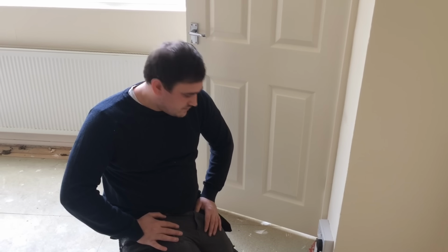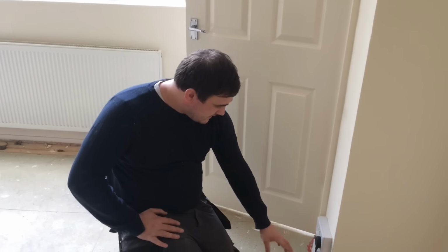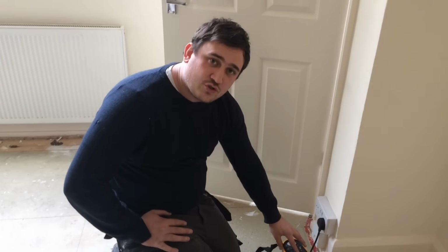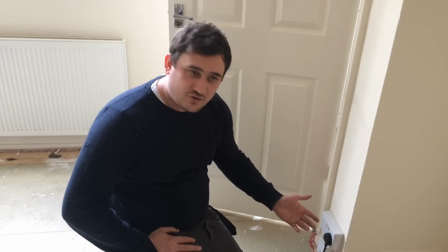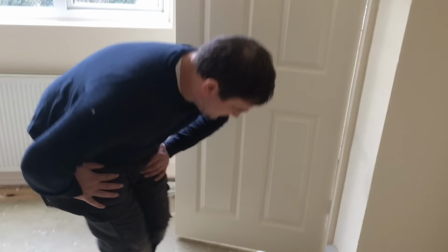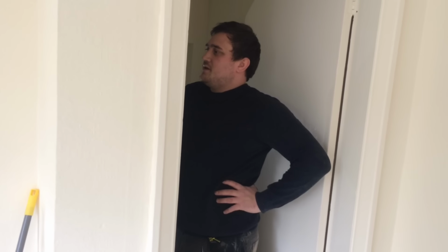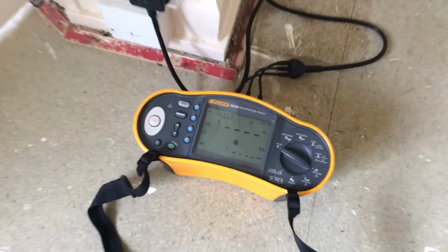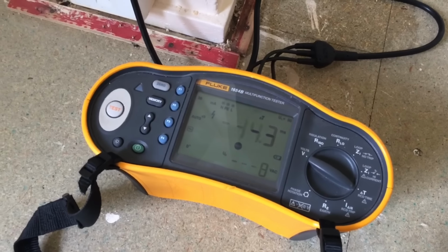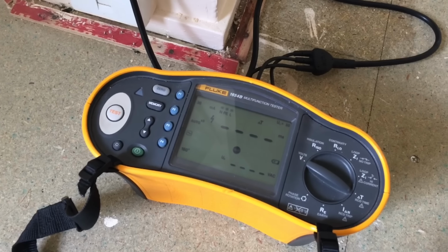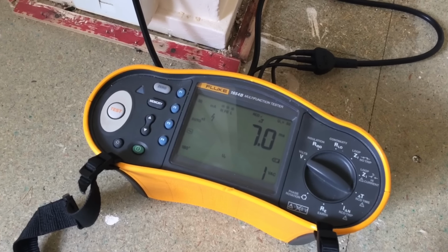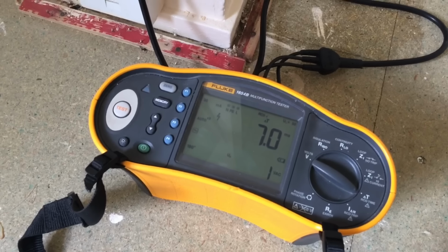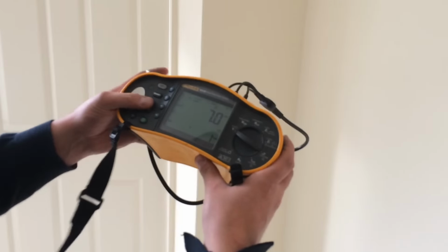Now we've completed our loop tests, we're now going to move on to the RCD tripping time tests. On this particular test I'm going to use the auto function, so it will test it at half times, 1 times, 5 times on both sides of the cycle, 0 degrees, 180 degrees. So all I have to do is to press the test button, do its thing, and we just have to keep resetting. Now it's finished, we come back to our tester, and as you can see we can scroll through the readings.